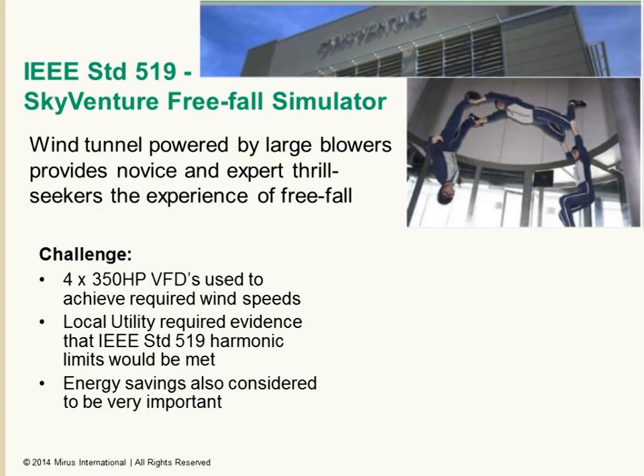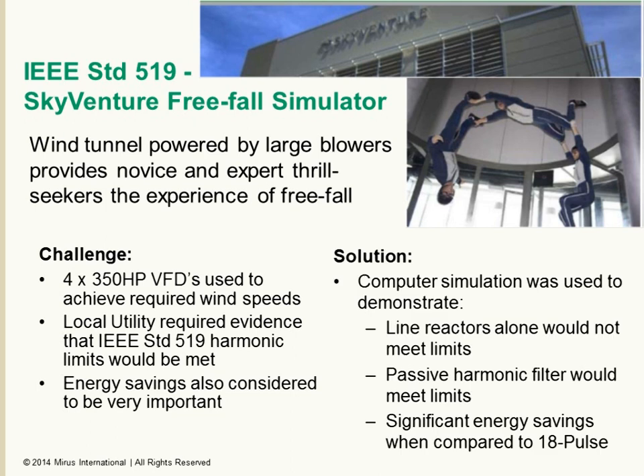Our first case study involves a skydiving simulator located in Montreal, Canada. I can say through personal experience that these simulators are a lot of fun. Large fans supplied by variable speed drives produce wind that results in the experience of skydiving. However, the harmonics drawn by the variable speed drives would exceed the limits required by IEEE Standard 519, so the local utility insisted that harmonic mitigation be applied.